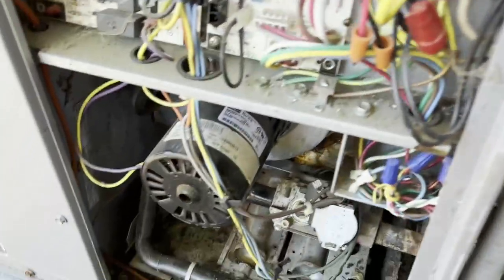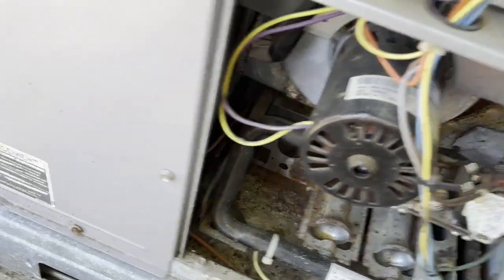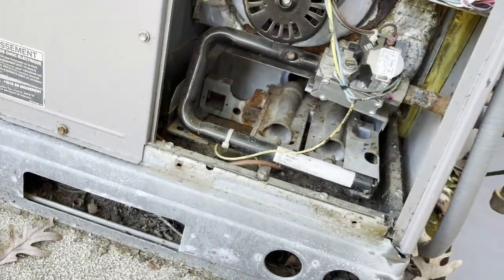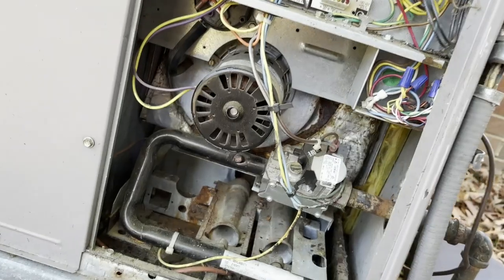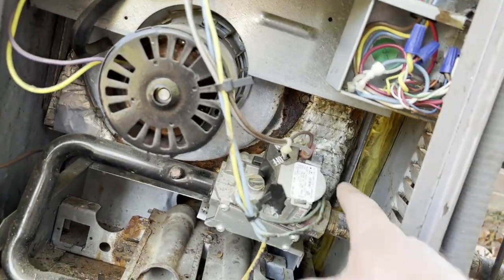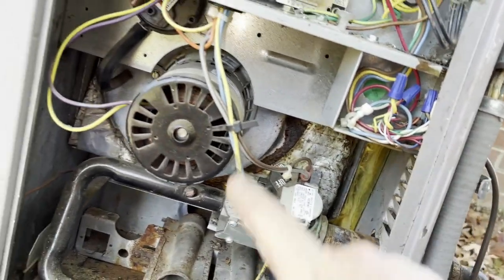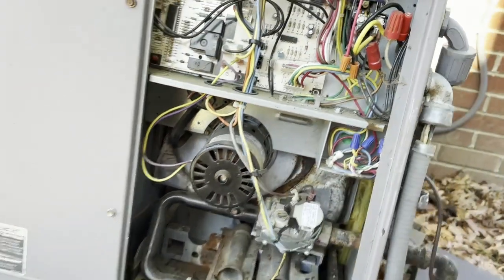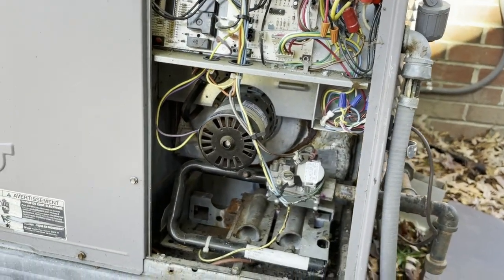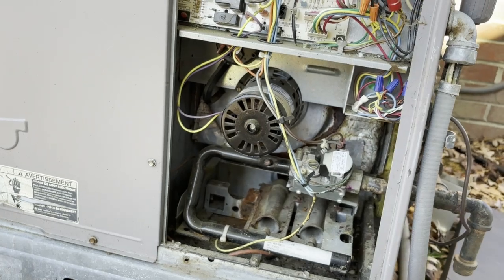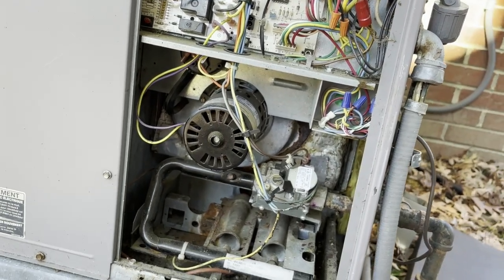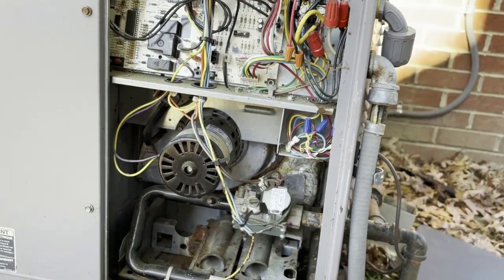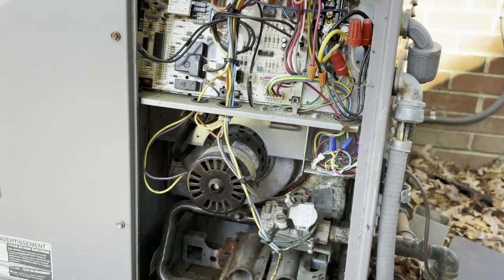Anyway, if you ever find a cracked heat exchanger in one of these things, make sure you get the heat exchanger and order the face panel or faceplate cover with it. Or you're going to be out of luck if that thing's rusted apart, because if it's rusted in there like that, that faceplate, once you get that motor off, it's going to crumble in your hands, and then you're going to come up short with a part you need and don't have because you didn't order it. So every time I order a heat exchanger for one of these things, I'll order the front faceplate too.